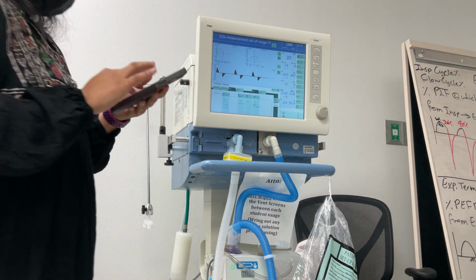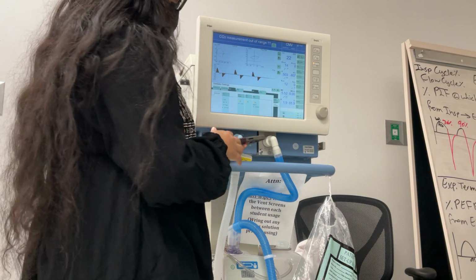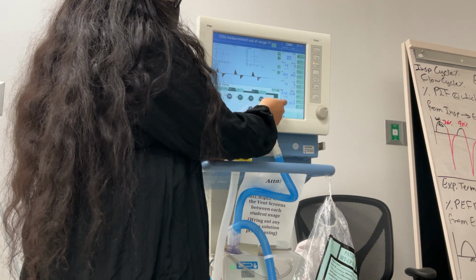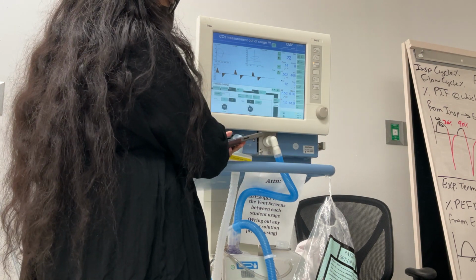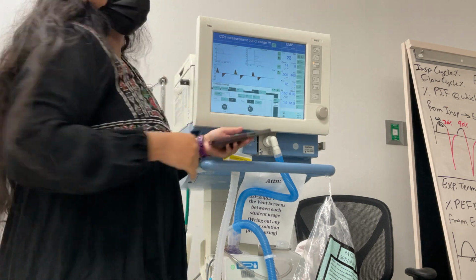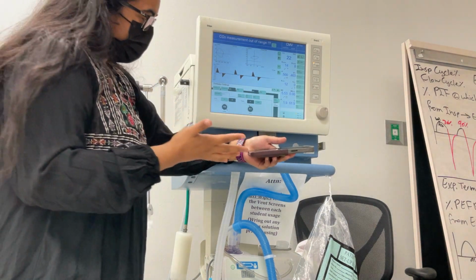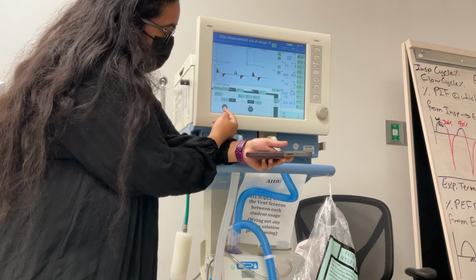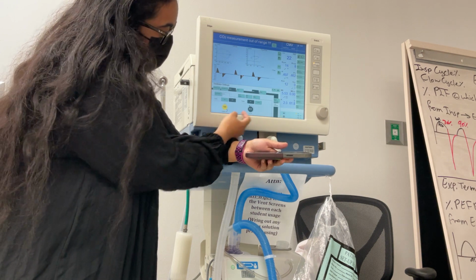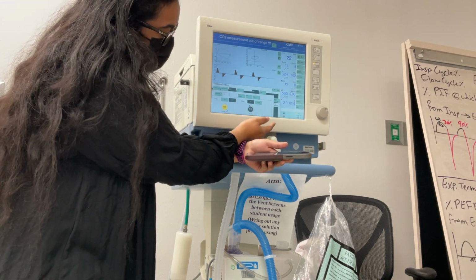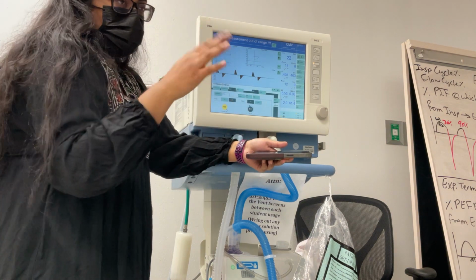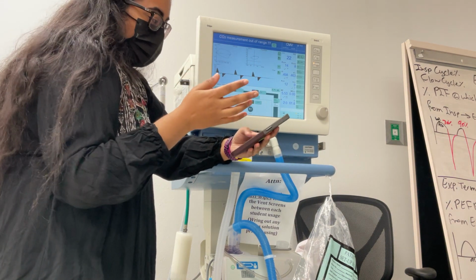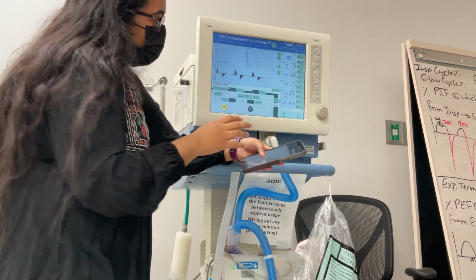Okay. So CMV is volume control on here. If you go to additional settings, you'll find your automatic tubing compensation that overcomes the work of breathing associated with your airway. If you turn it on, you can set the percent of compensation, and you can put in the ET tube or the trach size and whether it's an ET tube or trach, and it'll overcome the work of breathing associated with that airway.